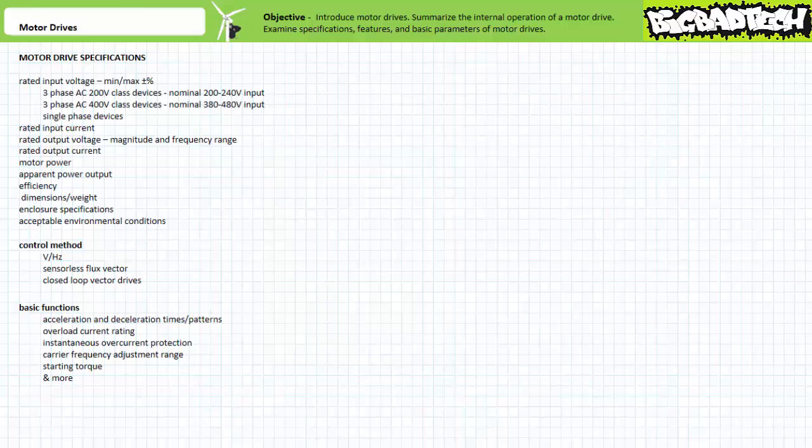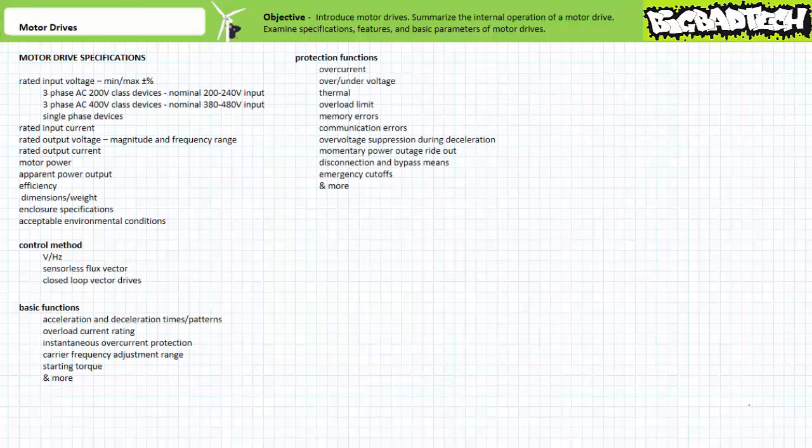Motor drives may also be specified with respect to functional and control specifications, like soft starts, acceleration and deceleration times and patterns, overload current rating, instantaneous overcurrent protection, carrier or switching frequency adjustment range, and starting torque. Motor drives may also be specified with respect to protection functions, like overcurrent, overvoltage, undervoltage events, thermal errors, overload limits, memory errors, communication errors, overvoltage suppression during deceleration, momentary power outage ride-out, disconnection and bypass means, and emergency cutoffs.